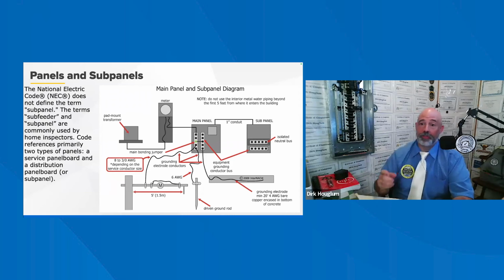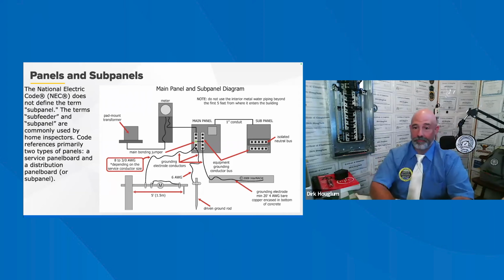Distribution panels or load side panels are downstream from the main panel containing the main service disconnect. In these panels, the neutral and ground should be separated and the neutral bus isolated. The only exception to this is existing detached structures where no metallic parts exist between the structure. In this exception, a connection between the grounding conductor and the metal case via bonding jumper is permitted.